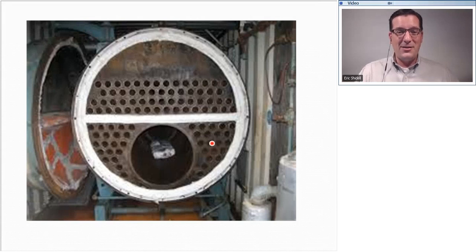This is our first pass of where the fire comes through. You can see the refractory material here has been patched up over time over the years. It hits that refractory, turns around, goes through these tubes, hits the refractory on the front side, turns back around, comes through these tubes, and the flue is located back there somewhere. I can't see it in this picture. But that's a shell and tube or fire tube boiler.